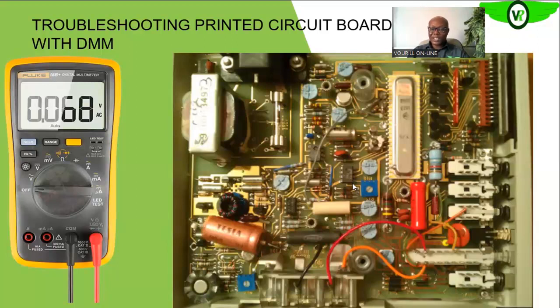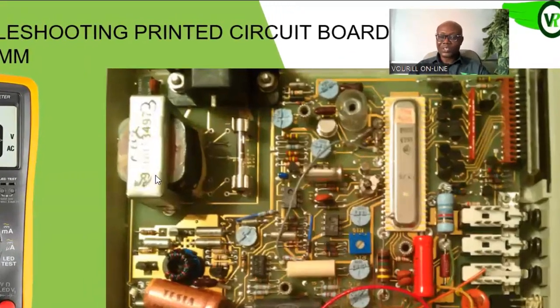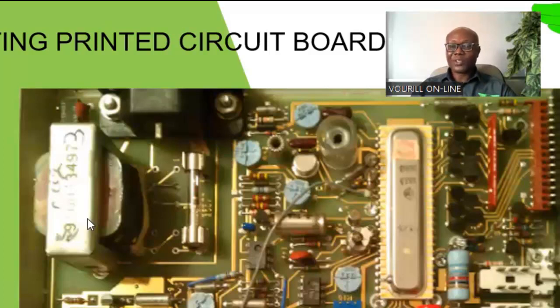Then the other test that you can do is the live test. In a live test, what you do basically is called voltage tracing. You know that AC comes into this transformer, so you test the input and be sure that you have that AC voltage. Then the output too: if it's a step down transformer, let's assume what is coming out of the transformer is 12 volts or 24 volts. That 24 volts, you are supposed to have it at the output of this transformer to be sure that the transformer is okay. So if you have that output, it means that the transformer is good. If you are not having it, the transformer is faulty.